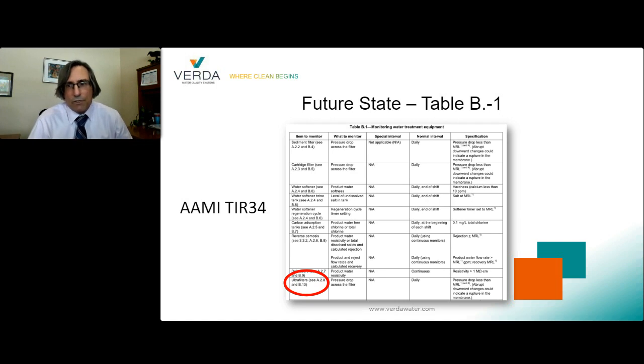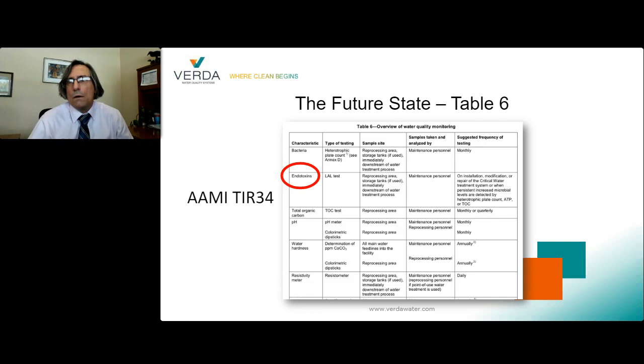What often happens with these filters is that before the pressure increases very much, they will blow out. This means they get a big hole in them, and all the endotoxins they were holding back now go straight to your instruments. If we go back to Table B1, we'll find that endotoxins are not something that are tested for on any regular basis, only if something else happens. If you have a filter blowout, it may be weeks before you're aware there's a problem.